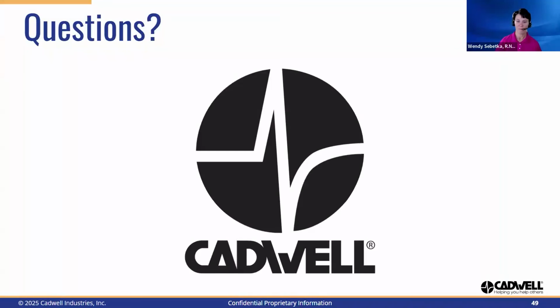Okay. So, for a mobile device, how far should it be kept from the EMG machine? So I think you're asking how far the device should be away from the EMG machine. Generally it's okay to have it within 2 to 3 feet away. There's really no set rule about how far away that device should be. If it's causing an issue and you're getting noise, try to move it around. Sometimes moving the cart to the head of the bed will make it better. Stretching the amplifier towards the patient will help. And if you're moving it around other areas like towards a power outlet, sometimes you're going to want to move it away from those items.